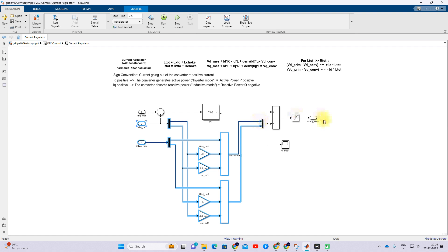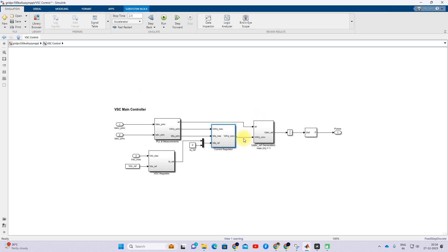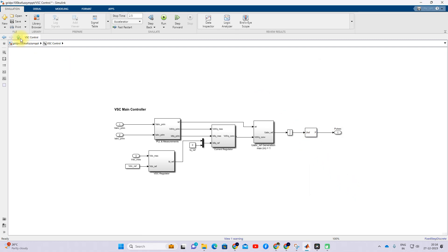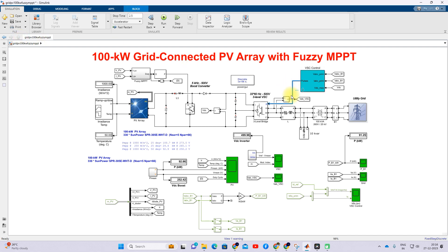Finally we have the Vd and Vq control voltages. We then convert Vd and Vq back into ABC form by applying the inverse Park transformation, and it is processed via the three-level PWM generator. The output pulse is then given to the three-level bridge, which converts the DC power into AC and pumps the power to the utility grid.